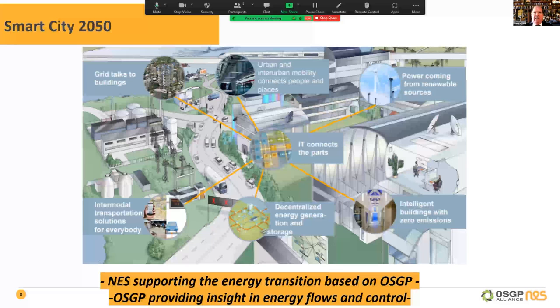And then the problem is that in that specific street, with maybe 20, 30, 40 solar panels at homes, there is more energy fed into the grid than the utility can transport. And more electrical cars charging at the end of the day. So they've got a problem there. That feeder, that transformer is not able to manage that environment. And even worse, the utility doesn't even know, because they don't measure the power quality, the voltages, and they don't have insight in the energy flows at the feeder level or secondary transformer at all.